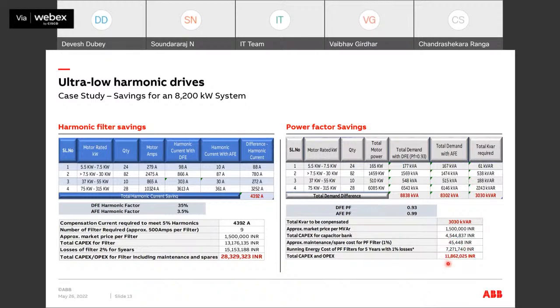It is 11 million. Additionally, we are going to insert 2 additional equipments in the electrical network, which is going to further reduce the efficiency of the network. We have to maintain both systems, harmonic filters and power factor compensation equipments, for a whole 20-25 years. While if you are using active front-end drives, definitely these 2 equipments go out of the system and your system becomes more effective and efficient.